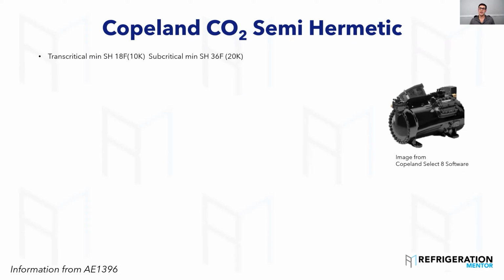So same thing, the semi-hermetic compressors, no different than Bitzer. For that transcritical compressor, minimum superheat is 18F, 10K. Subcritical, that low temp, is 36 Fahrenheit or 20K. You have to remember that. You have to be checking that, because when you start getting below that, you're starting to cause damage to the compressor.